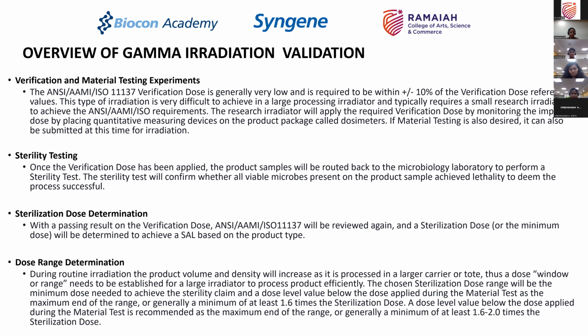So what do you do? You take it to a lab irradiator, a small research irradiator, and then you subject it to low dose rates of whatever has come out from the table, and then use dosimeters to find out what is the actual level of dose which you have imparted to the product. Based on this, you can determine whether you have effectively achieved your sterilization levels or not. So you have to conduct these small scale studies before you subject the larger material to irradiation itself.